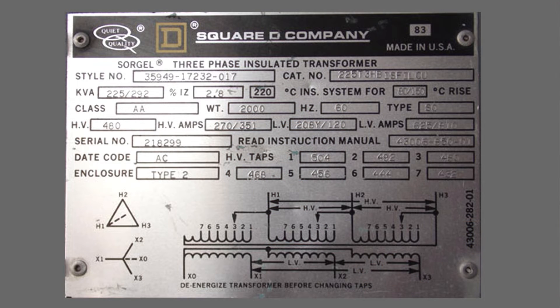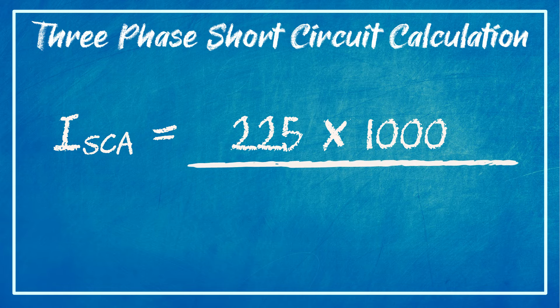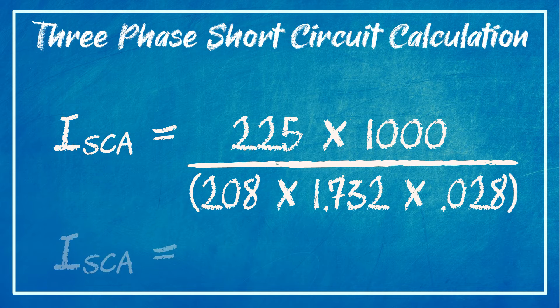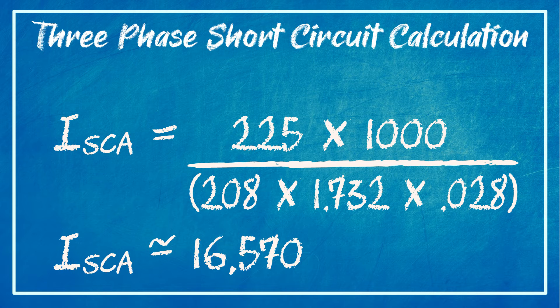Here's our next transformer. Notice that on this particular nameplate, there are dual ratings, and the rating we choose depends on the selected temperature rise. We will use the numbers on the left, which are for a 60 degree Celsius temperature rise. This particular transformer is rated at 225 kVA, 208 volt three-phase for the secondary, and 2.8% impedance. Plugging that into our formula: 225 times 1000 divided by (208 times 1.732 times 0.028) equals about 16,570 amperes.